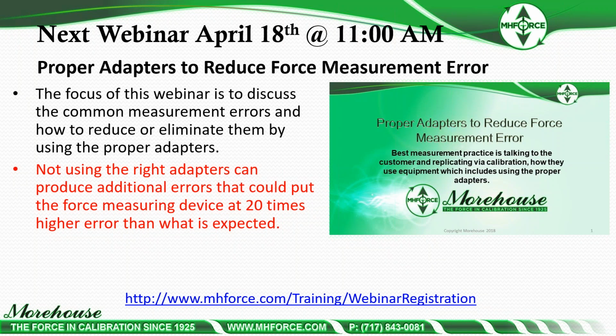And unfortunately, what ends up happening, which I don't like, is that in our lab we calibrate an S-beam cell with our tension adapters with two sphericals per the ISO 376 Annex recommendation, and we're going to get better results than the person who then uses those out in the field with threaded rod. But that's what we do. We're using those adapters. We want to replicate use, but at the same time, if we're not getting tension adapters, we're going to use ours and give the best possible measurement result.